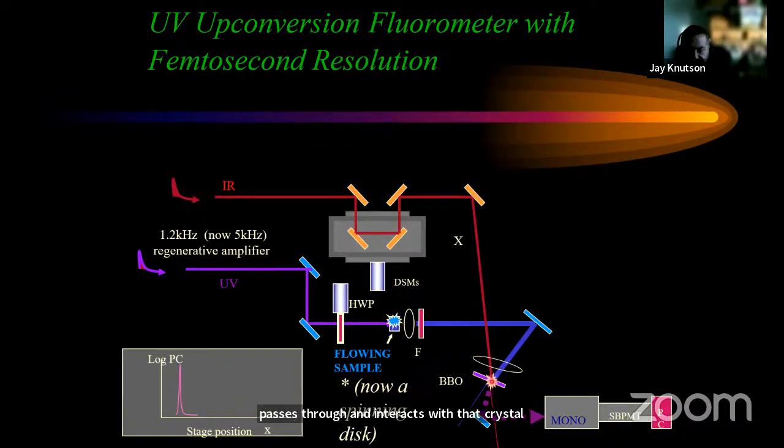And you can imagine the fluorescence as being like turning on a garden hose. As the water is flowing, you're taking a cup and swinging it quickly through the path of the hose and collecting an amount, and then passing it to somebody who slowly weighs how much you've achieved. So now you don't need a fast photomultiplier. Now you're simply quantifying the amount that you've chopped out of the stream of fluorescence. This gives you unprecedented timing, something similar to the pulse widths themselves.